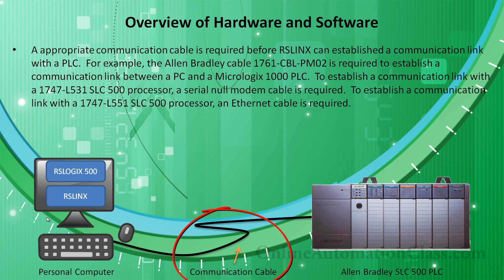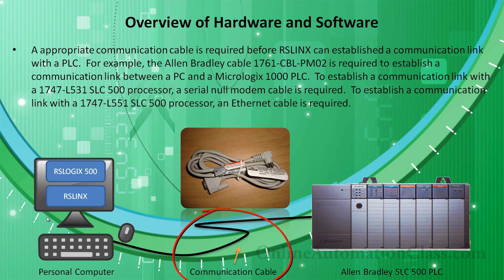An appropriate communication cable is required before RS-Linx can establish a communication link with a PLC. For example, the Allen-Bradley cable 1761-CBL-PM02 is required to establish a communication link between a PC and a MicroLogix 1000 PLC.